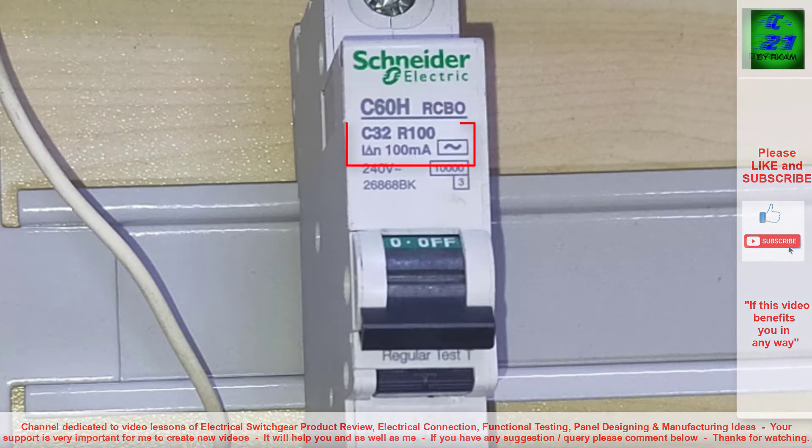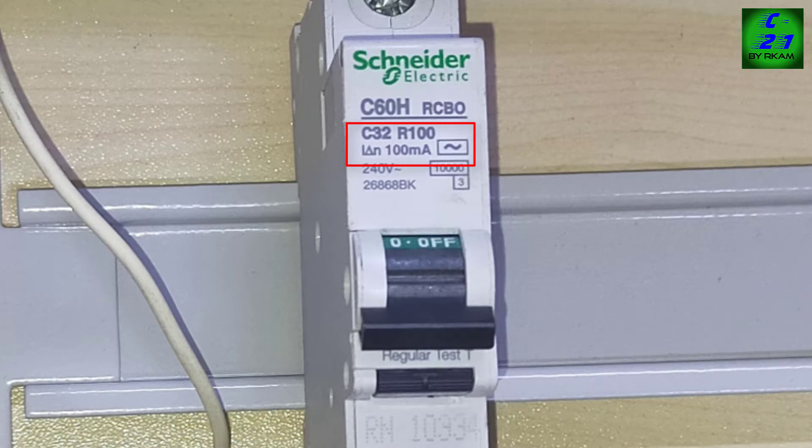Here I have a 32A 100mA rated breaker. So 32 is the overload limit and 100mA is the earth leakage sensitivity. Here we can see one test button, this is also for functional testing. This 10000 means this breaker will carry 10000A in fault condition without damage, and we can use this up to 240 voltage application, that is also mentioned here.